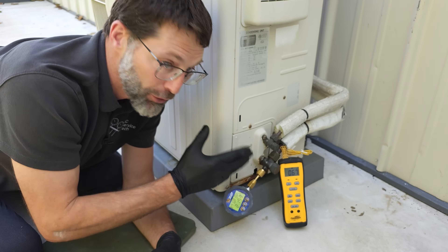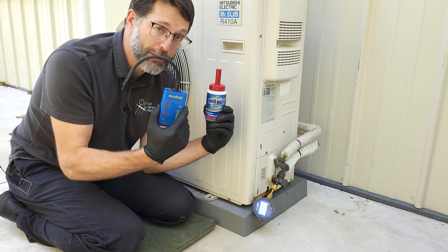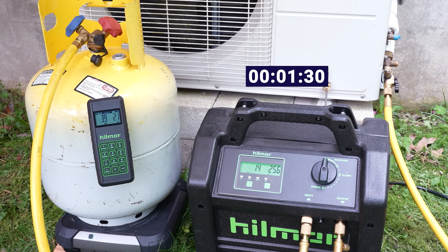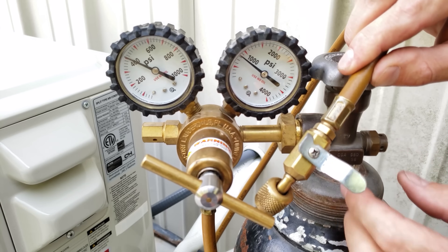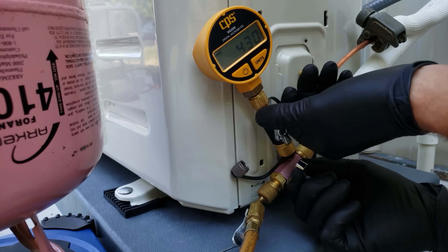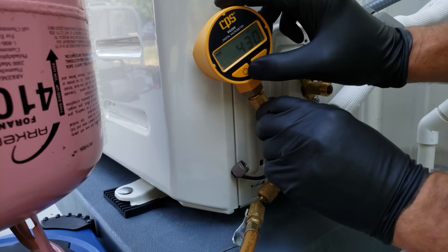After you've located the leak using an electronic leak detector or non-corrosive bubble leak detector, you're going to have to recover the full refrigerant charge out of the system in order to fix the leak. Then you're going to have to pressure test it, vacuum it, and charge the full refrigerant charge back into the system again, breaking the vacuum with refrigerant from the bottle.